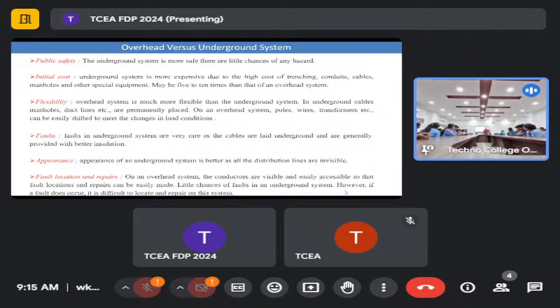You see, I am sharing some experience with you. During my long 5 or 6 years of working experience in Agartala as a superintendent engineer under West District, I have laid so many lengths of cables. I never found during my entire tenure that a fault had taken place because of an inherent defect of the cable or from any foreign element. But every time there was a power supply disturbance in any part of the city, I found that it was not our fault.